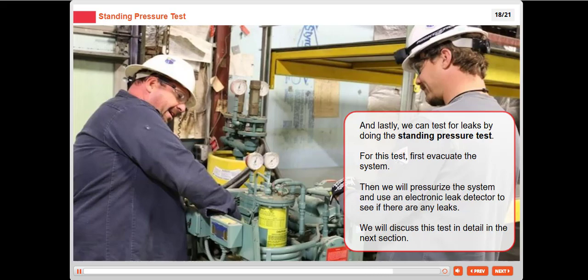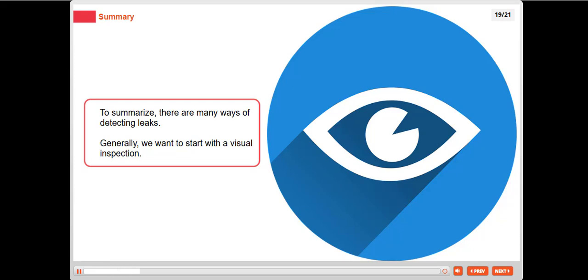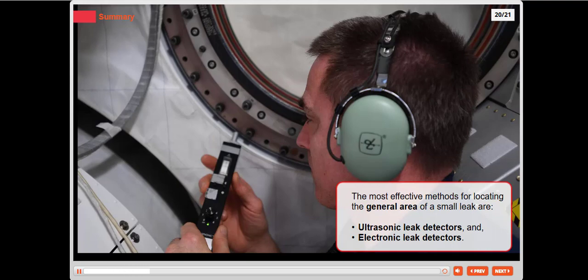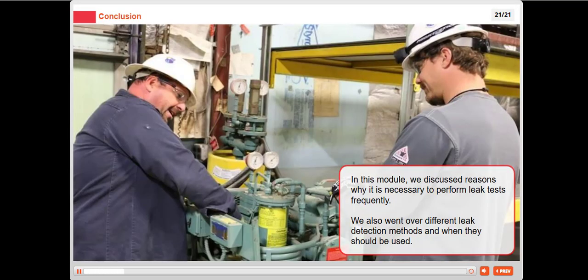To summarize, there are many ways of detecting leaks. Generally, we want to start with a visual inspection. The most effective methods for locating the general area of a small leak are ultrasonic leak detectors and electronic leak detectors. In this module, we discuss reasons why it is necessary to perform leak tests frequently. We also went over different leak detection methods and when they should be used.